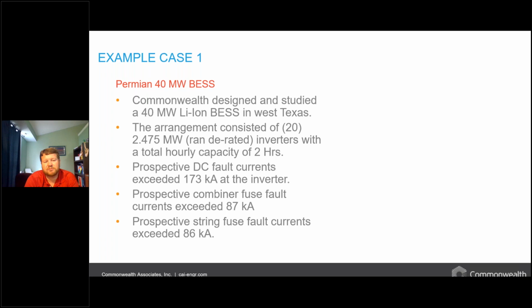And this arrangement consisted of 20 different inverters that are all rated at 2.475 megawatts each. And the target capacity of this battery energy storage system was 2 hours. And what that means is we're taking a central inverter design where we're taking a very large inverter and putting a lot of batteries behind that to be able to get to that 2.475 megawatt output range. And we want to be able to do that for the energy density requirement of 2 hours. But what we're seeing is when we put enough batteries in parallel and in series to give that energy density at the appropriate voltage ratings of the inverter, in this case it was maximum at 1500 volts DC, we're seeing very high fault currents.